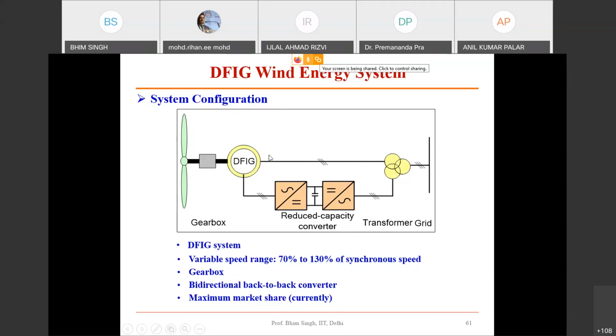So 30% of that 120 or 125% you can generate from there. So 30% of 125 means around 35% power you generate from here, and 120% you generate from here. So the machine is capable. Let's say if you have around 150%, so if you have a turbine of 1.5 megawatt, you have to take a generator of only 1 megawatt. The losses are for 1 megawatt, but it's generating 1.5 megawatt.